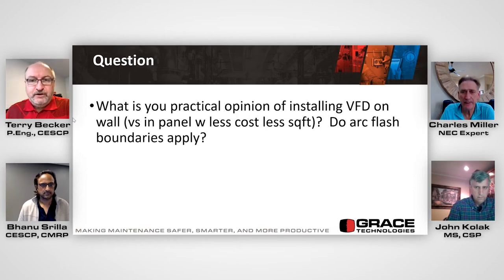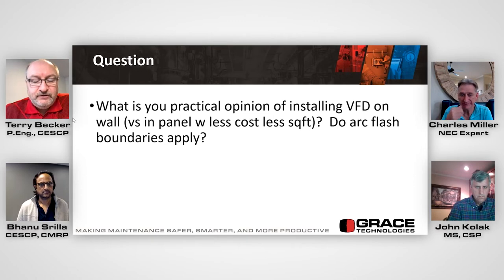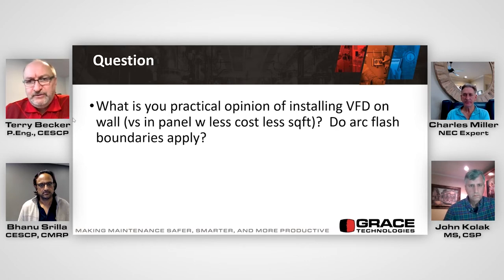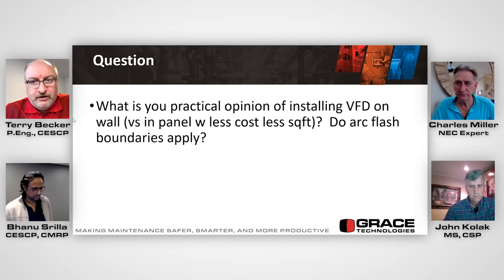I think the question here is: if you have normal equipment conditions, the arc flash boundary doesn't exist, right? A VFD can be mounted on a wall and be operating, completely safe. There's no shock potential to using the VFD or touching the keypad. Well Terry, it's running and making noise. Well yeah, it's going to cool itself, there's going to be fans. So in normal equipment conditions, we do not need arc flash PPE. The arc flash boundary doesn't exist.